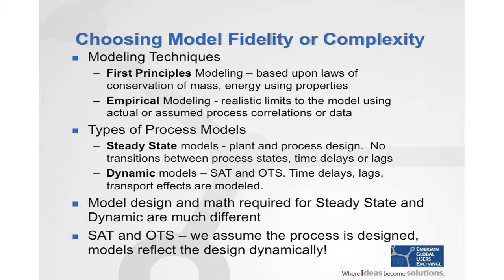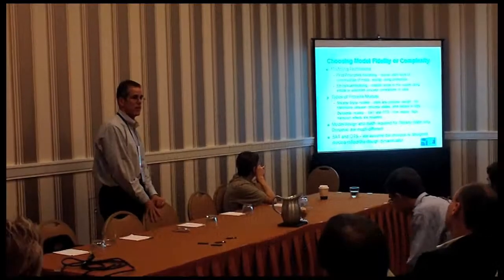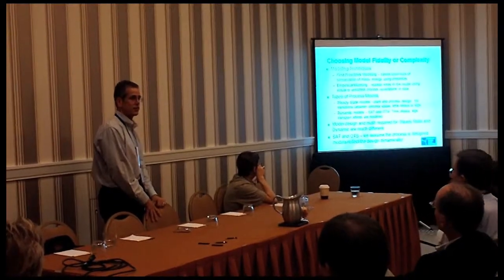You really need a dynamic model for software acceptance testing and operator training. The characteristic of a dynamic model is it's built from the ground up with a mathematical relationship, so it handles time delays, lags, transport effects, and dead times in the process.